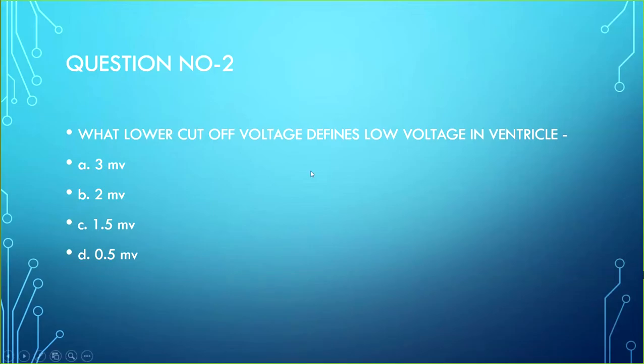Poll question 2: What lower cutoff voltage defines low voltage in the ventricle? The correct answer is less than 1.5 mV. In the atrium the cutoff is less than 0.5 mV, and in the ventricle it is less than 1.5 mV.